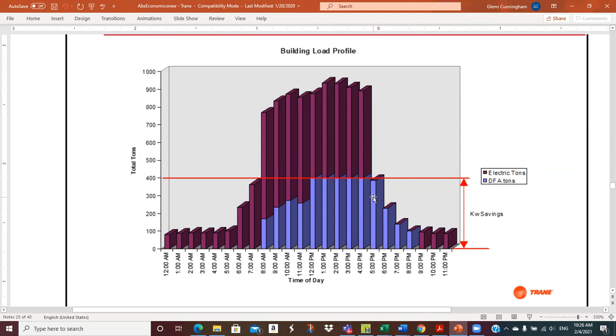And so once the load is 400 or less, we're just going to operate the absorber until we get to the end of the peak period, and then we're going to shut it down and go back to the centrifugal because it's cheaper. So, I mean, we're just doing our best.